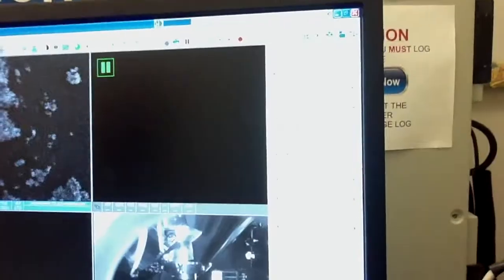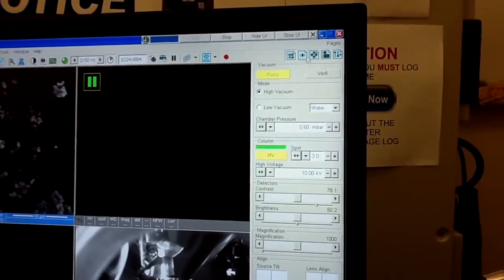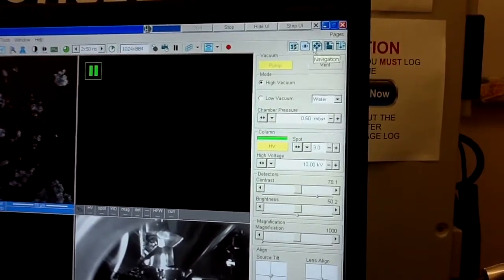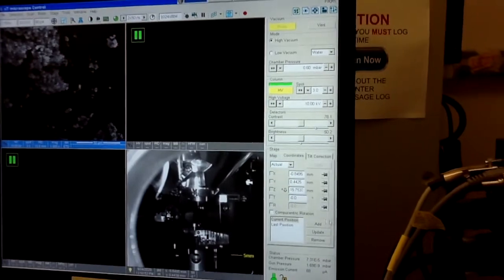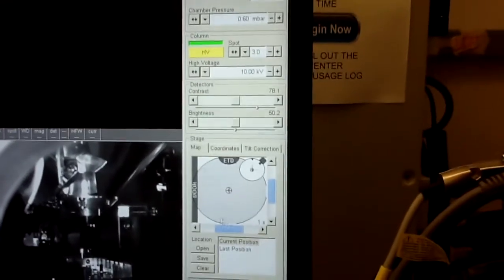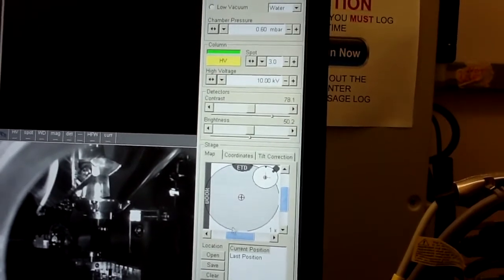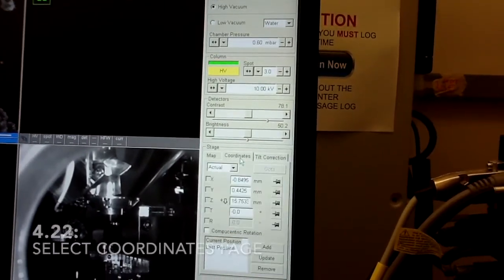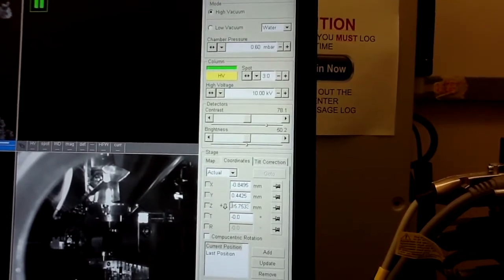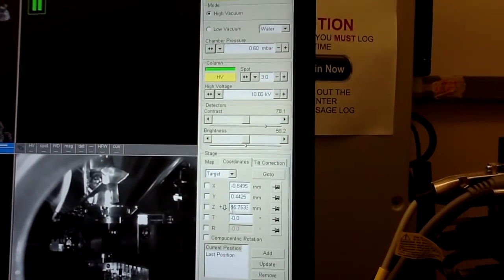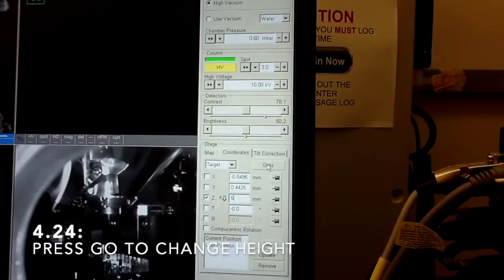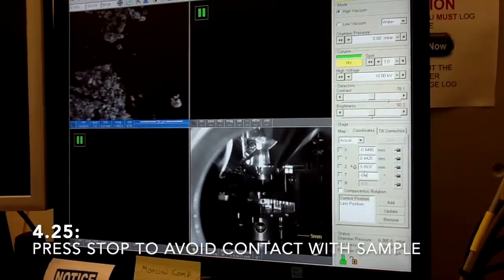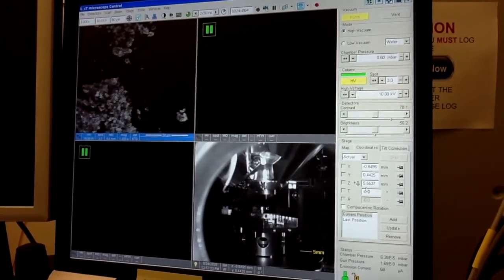Now, when you already linked your height to the focal working distance, to move to the 5 millimeter mark, the easiest way is to go to the navigation menu. Right now we are in the beam control menu. There are five menus here. Beam control, detectors, navigation, processing and alignment. So go to the third one, the navigation menu. And you will see these controls right now. One, for example, here in the stage, there is a menu which shows a map, which will help you. You can store even locations. You have many samples. You can, for each of them, store the location and then automatically go to this location. So this is very useful feature. But right now we want the coordinates page. And instead of, right now, a Z height is at 15.75 or 15.8. Type 5 here. And then press go. You will see that the stage is moving up. We reached the limit. It's 5.5 millimeter, but this is good enough. Between 6 and 4, this is a good working distance.